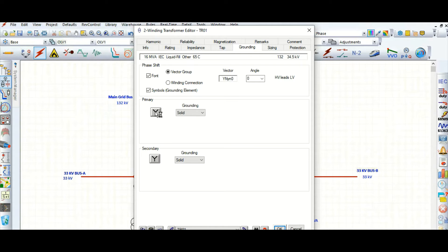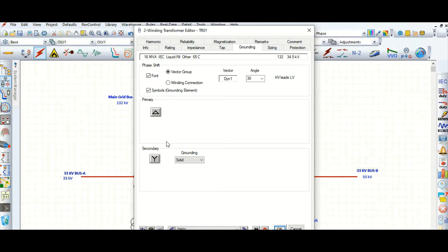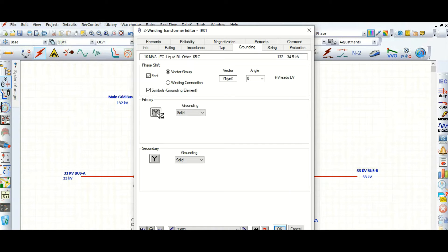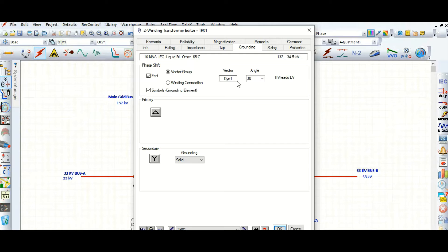Suppose this is a delta-star transformer. You can toggle between delta and star: the primary connection is delta and the secondary is star. If you have a star-delta transformer, set star on the primary and delta on the secondary. I want to assign a delta-star transformer. Before that, let's look at the vector group — this is dyn1. You can change the vector group by changing the angle from the drop-down list.